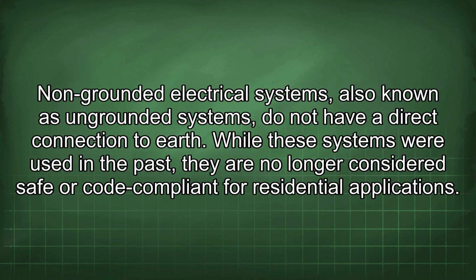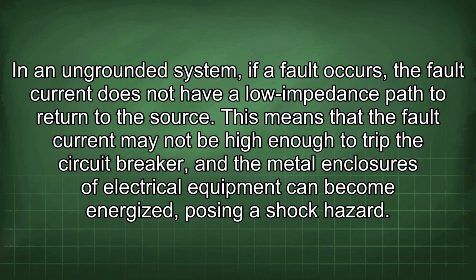Non-grounded electrical systems, also known as ungrounded systems, do not have a direct connection to earth. While these systems were used in the past, they are no longer considered safe or code compliant for residential applications. In an ungrounded system, if a fault occurs, the fault current does not have a low impedance path to return to the source. This means that the fault current may not be high enough to trip the circuit breaker, and the metal enclosures of electrical equipment can become energized, posing a shock hazard.